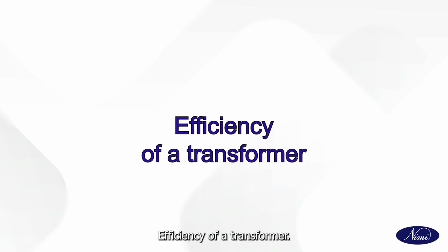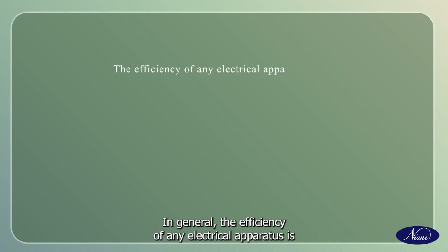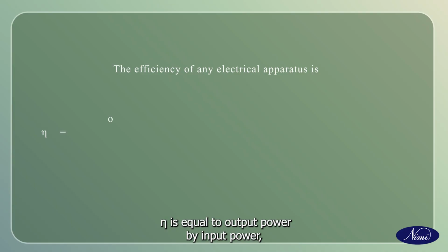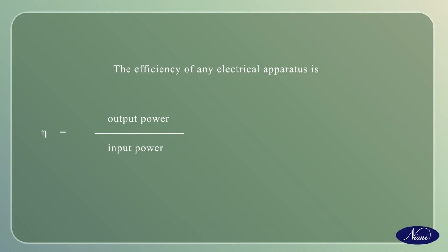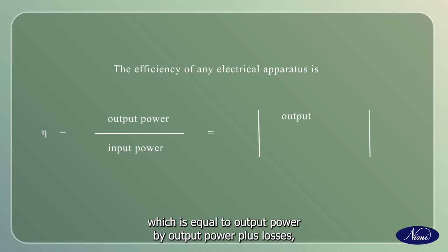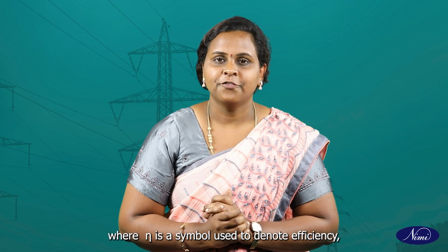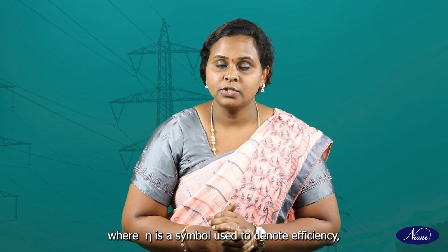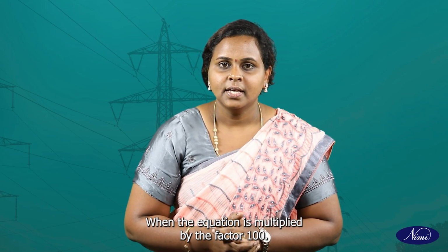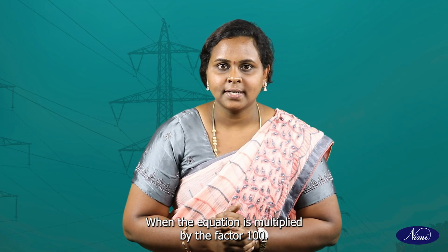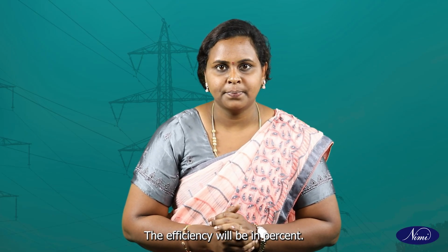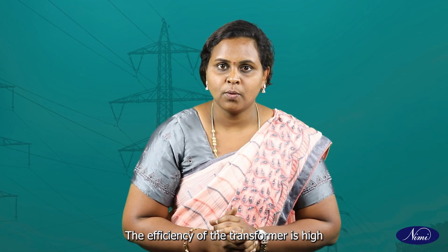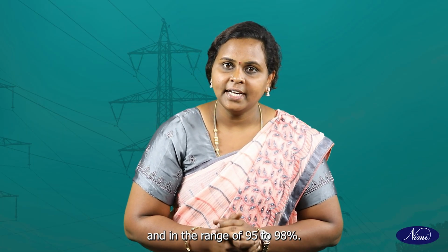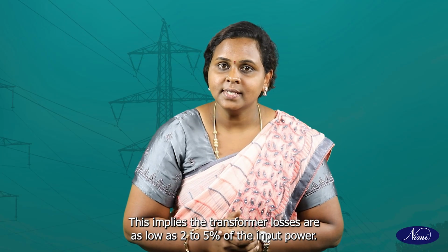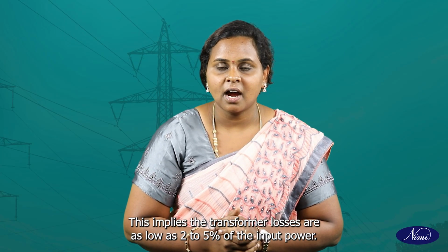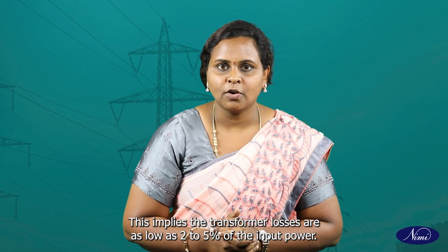Efficiency of a transformer. In general, the efficiency of any electrical apparatus is eta is equal to output power by input power, which is equal to output power by output power plus losses, where eta is a symbol used to denote efficiency. When the equation is multiplied by the factor 100, the efficiency will be in percent. The efficiency of the transformer is high and in the range of 95 to 98%. This implies the transformer losses are as low as 2 to 5% of the input power.